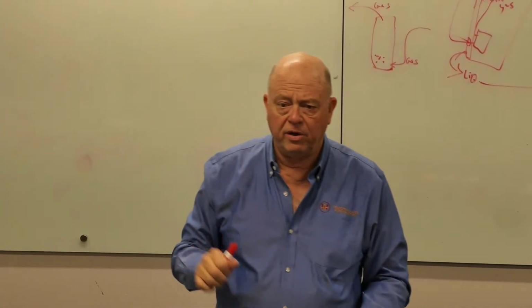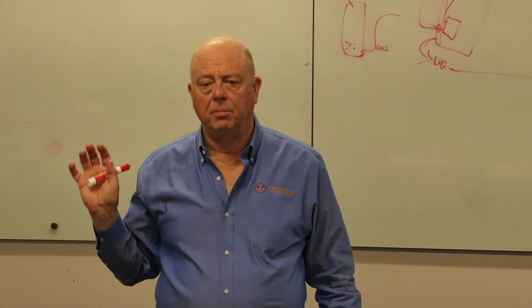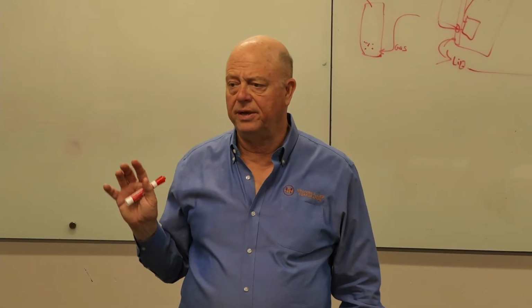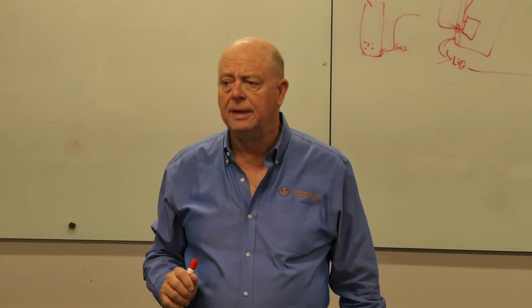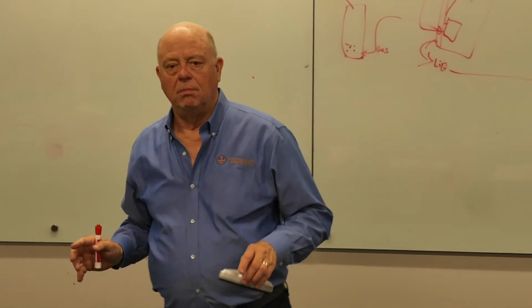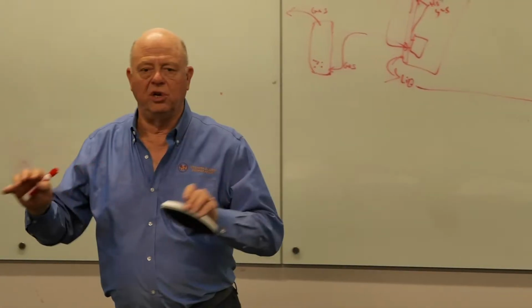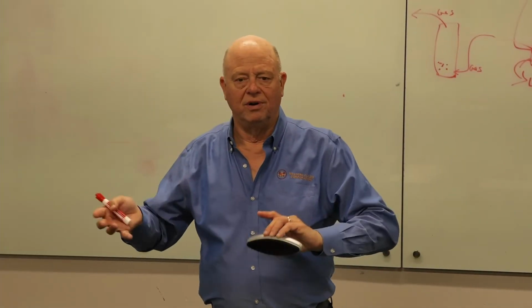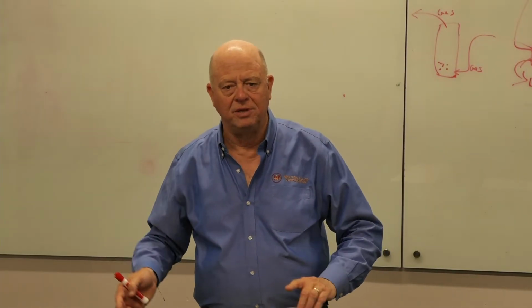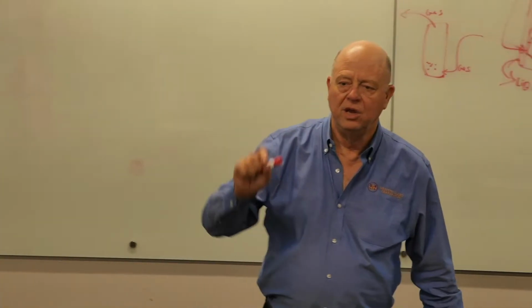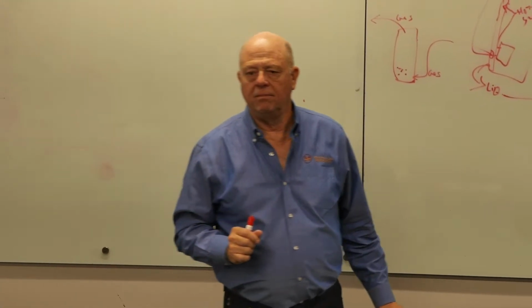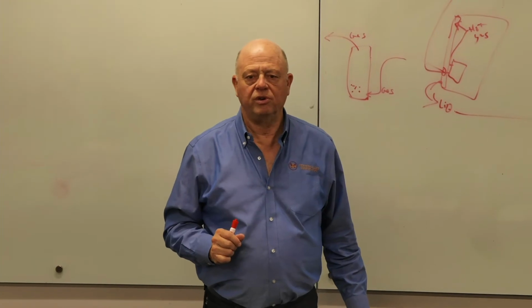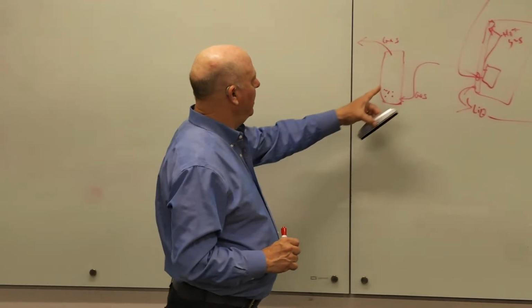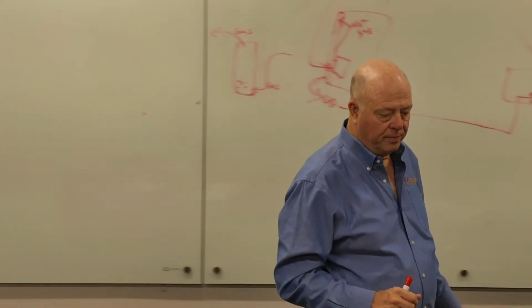Now, the plan is, we'll see how this works, but the plan is to finish today talking about heat pumps. Because a heat pump has two directions it can go. There's a switchover. And when the switchover happens, if something doesn't work right, you can end up with a little bit of liquid refrigerant going where it's not supposed to go. And that's why we will have an accumulator. We'll talk about that.